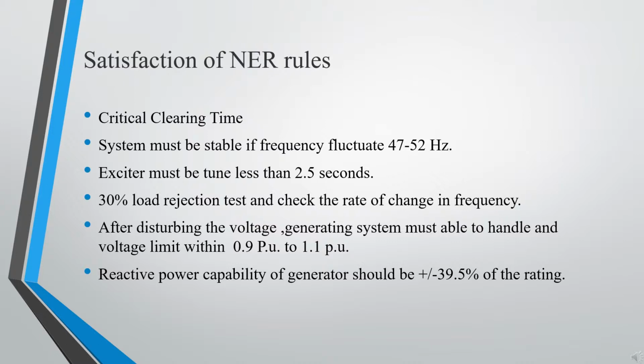and we have used MATLAB to plot the waveform of the frequency after rejecting 30% load at the point of connection, in both cases, hydro generation only and PV generation only. In the case of PV generation, the frequency gets a little bit higher than in hydro generation. We also worked on the voltage disturbance test, in which we have to trip the feeder between the point of connection and the grid. We have done it and checked the voltage profile at every bus, and the voltage profiles are within the limit of 0.9 to 1.1, which is the emergency situation.